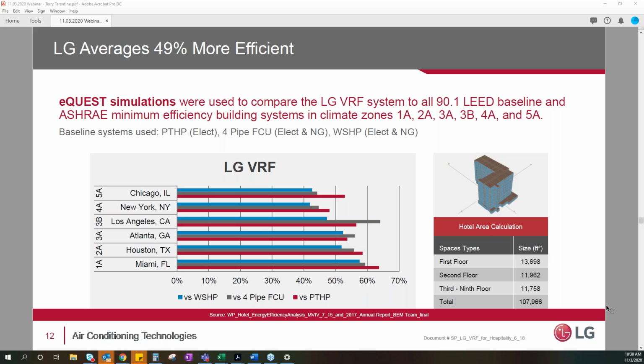And this was eQuest, an energy program, and we're taking Chicago, Illinois as our source here for our market. And here is just a comparison of water source heat pump, fan coil units, and PTAC heat pumps. You can see easily PTAC heat pumps are the least efficient system out there. Again, while they're the least expensive to put in up front, they're the most expensive to run.